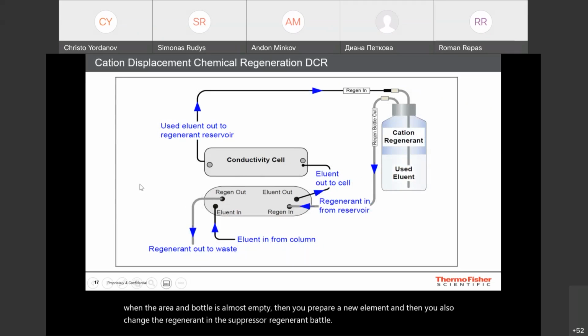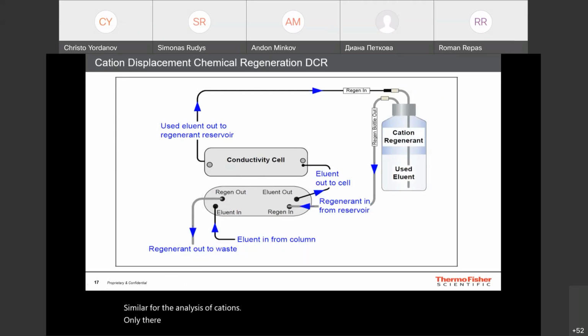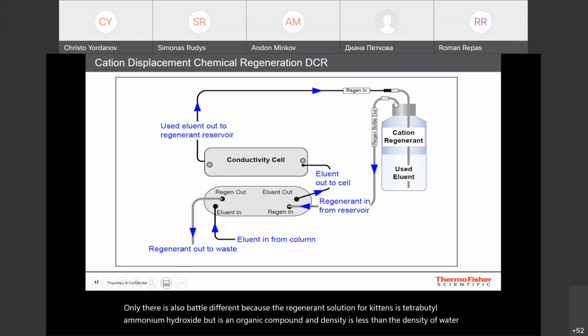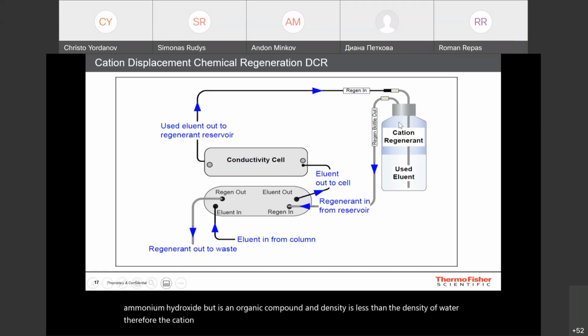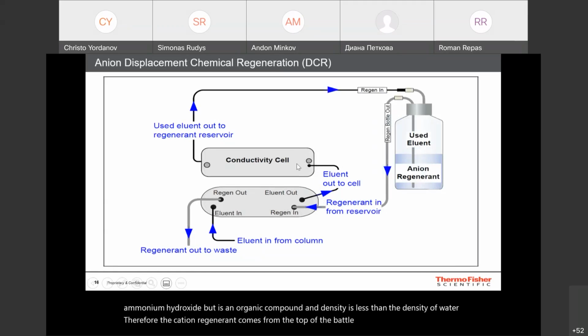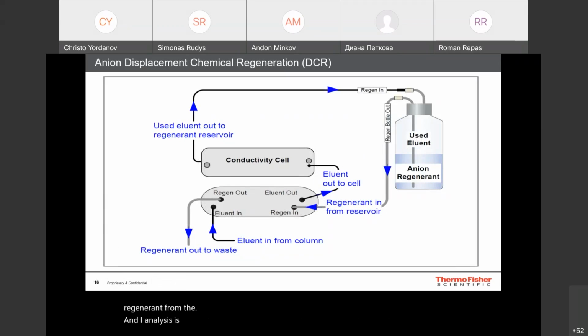Similar for the analysis of cations, only there is also a bottle different, because the regenerant solution for cations is tetrabutylammonium hydroxide, which is an organic compound, and the density is less than the density of water. Therefore, the cation regenerant comes from the top of the bottle. In the previous case, the regenerant from the anion analysis is practically sulfuric acid with higher density than the water. Then this is mostly coming from the bottom of the bottle.